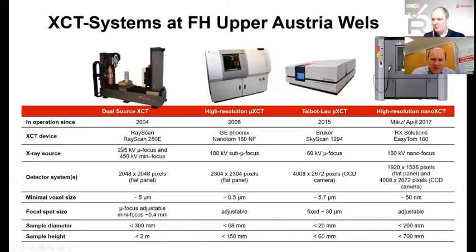We have 4 CT systems at the University of Applied Sciences in Wels. We have a dual source CT system, which will be upgraded in the next months. There will be a completely new CT system concerning the electronics and the reconstruction software, available at the end of this year. Then we have a high resolution CT system, and a very special Talbot-Lau grating interferometer CT system. Our highest resolution we can get with the nano XCT system, where we can have a voxel size of something like 50 nanometers and resolutions of something like 600 nanometers.